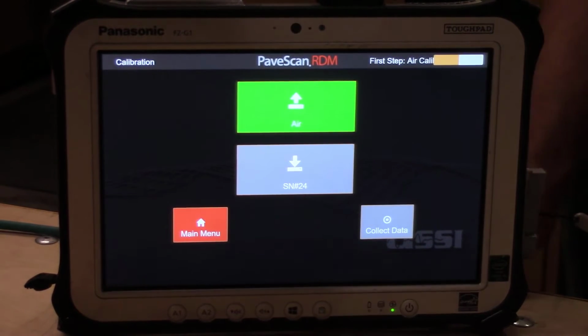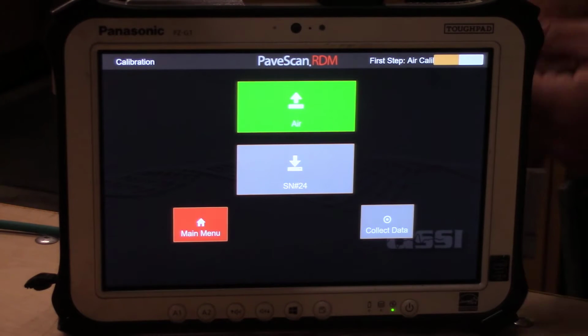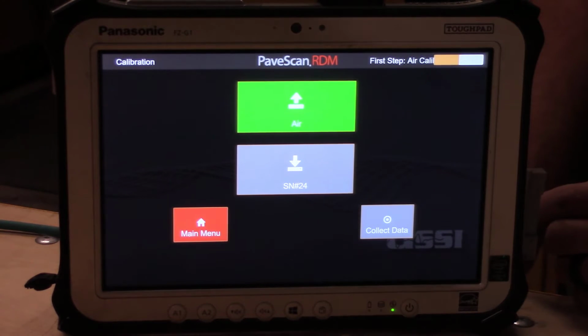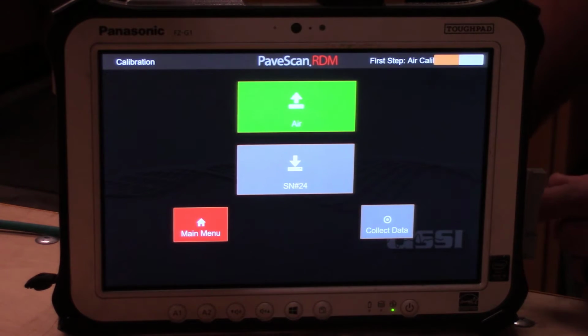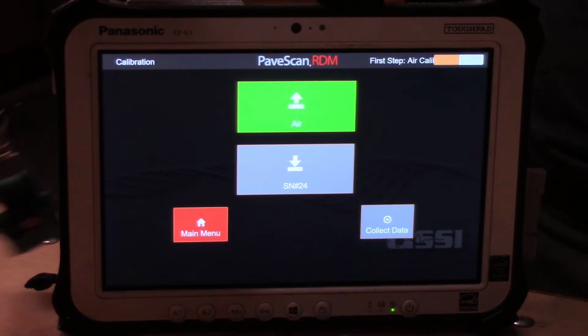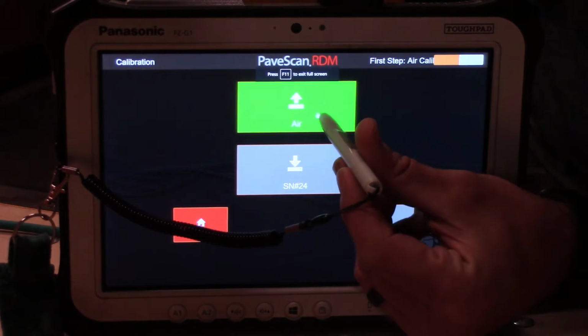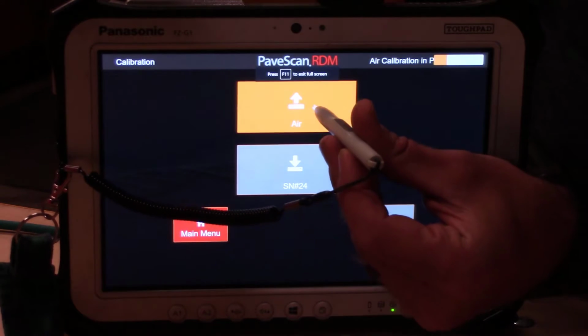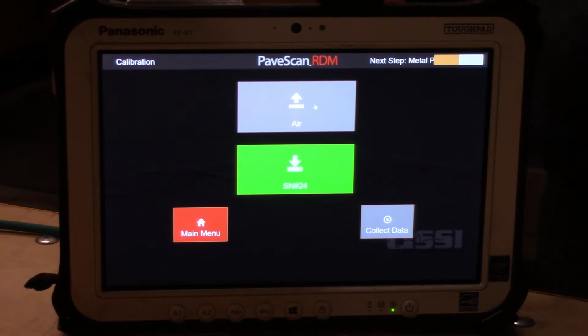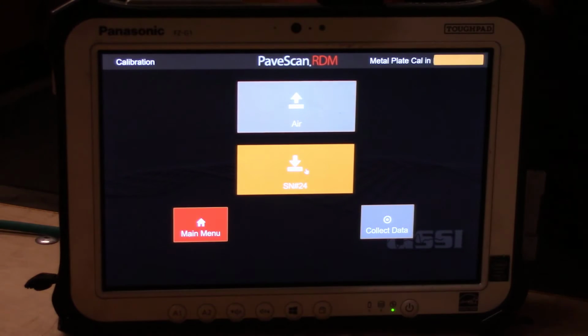Once the sensors are warmed up, we still have to go through the calibration process, even though this data isn't actually used for anything - this will change once we have the puck testing module. You just press the air calibration, even though this data doesn't mean anything; it's just to get into collection mode. The same applies for the metal plate calibration - once that turns green, we're doing that calibration even though no metal plate is actually being measured.